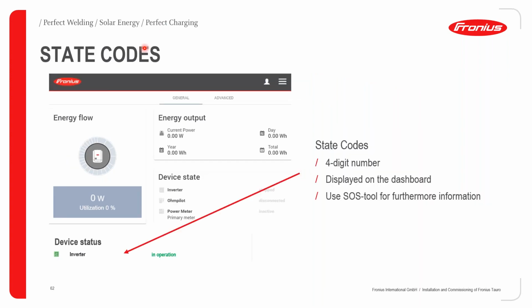Yes, so in terms of state code, as in the case of the Gen 24, as we explained in previous webinars, the state code this time comes in 4 digits, contrary to what usually happens with our Snap inverters. They're usually 3-digit codes, and they come in different error classes or state code classes. But in this case, it doesn't follow that process. What you get is a 4-digit number, and it comes in ascending order. So let's say you have a state code of 1234. If you now get another state code, it will come in as 1235. So it comes in ascending order, and of course, it's always displayed on the dashboard of your monitoring device.